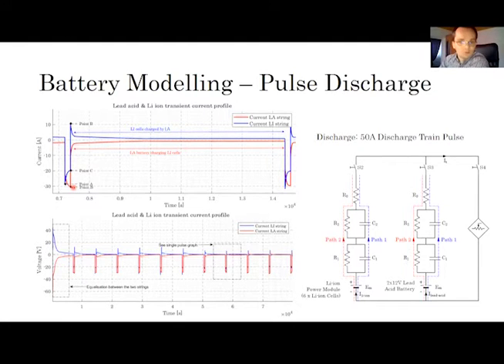When I stop discharging, between points C and B, you can see the lead acid string is charging the lithium-ion one — that's happening at point B. Here I'm applying a pulse train discharge of 50 amps, so you can see these kinds of effects.